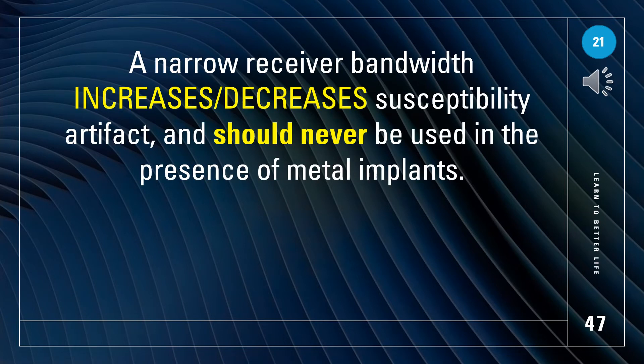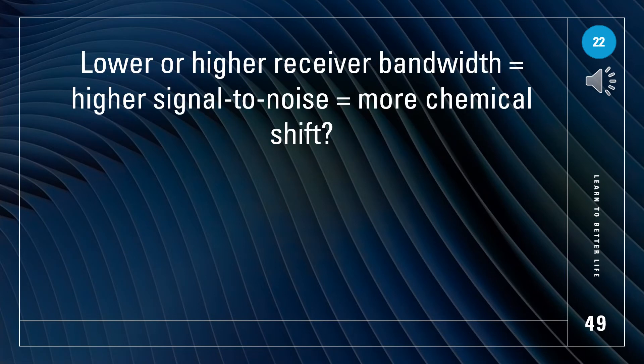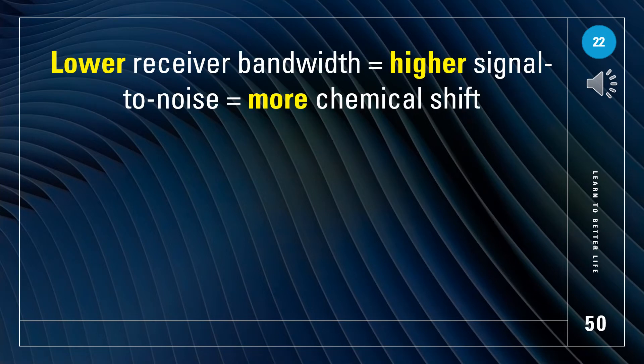A narrow receiver bandwidth increases susceptibility artifact and should never be used in the presence of metal implants. What are the effects of receiver bandwidth on signal-to-noise and chemical shift? Lower receiver bandwidth leads to higher signal-to-noise and more chemical shift.